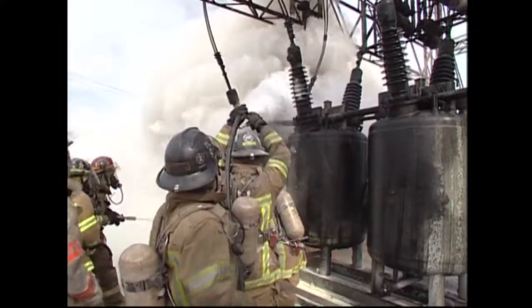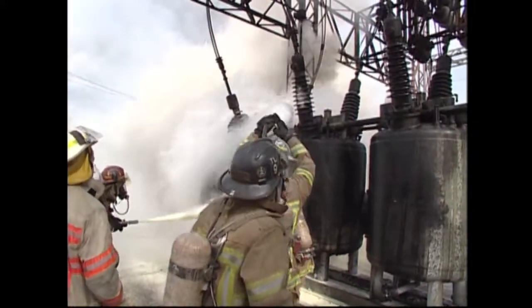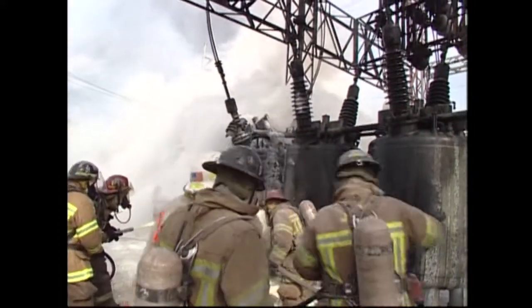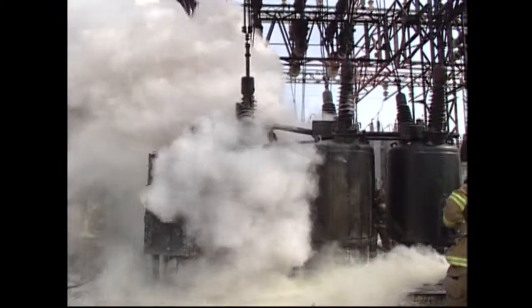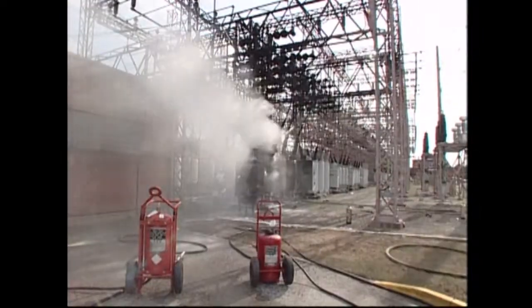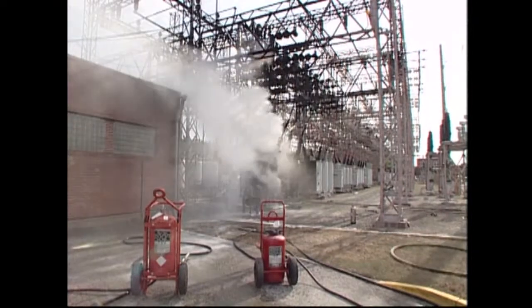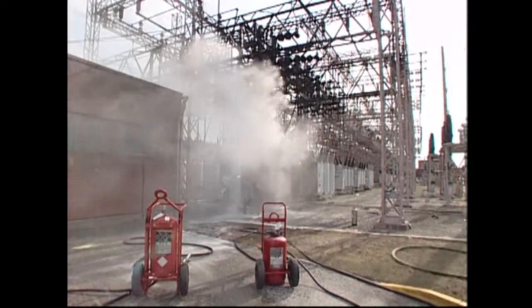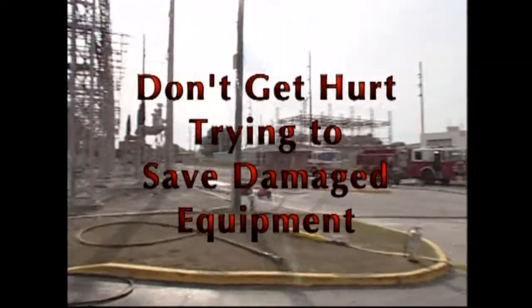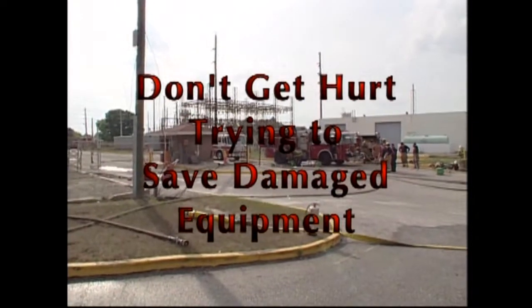They were able to de-energize this bank that we're under, but not totally the entire facility here. We marked off an area we felt safe to put foam and our Purple K dry powder extinguishers, try to knock it down. As previously stated, equipment which has been severely damaged by fire most likely will not be repaired, and the utility company doesn't want anyone being injured in trying to save it.